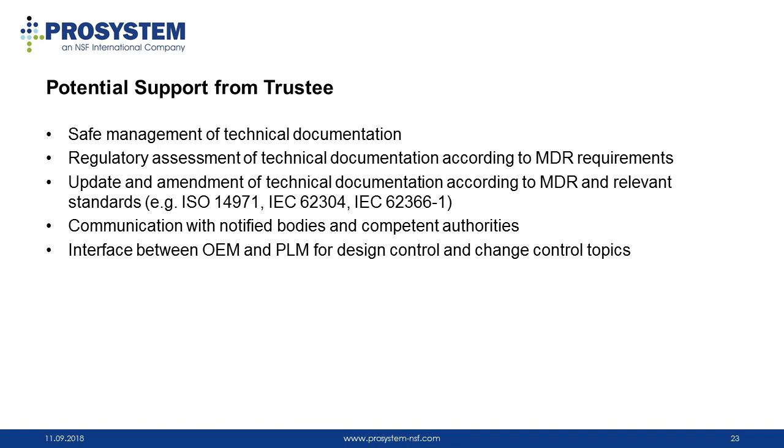The trustee is involved in communication with notified bodies and competent authorities and can also be involved when it comes to audits, for example, or requests for review of technical documentation. And the trustee can be the interface between the OEM and the PLM when it comes to design control and change control topics. The OEM only has to be involved when the solution is not clear. Then the OEM might have to step in.